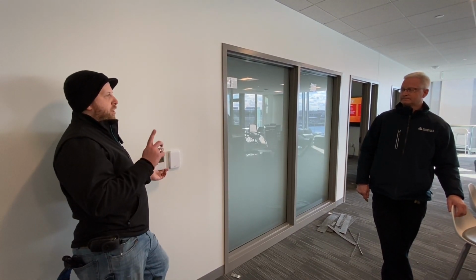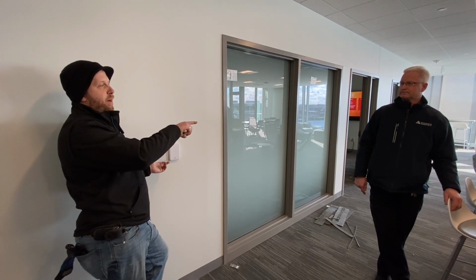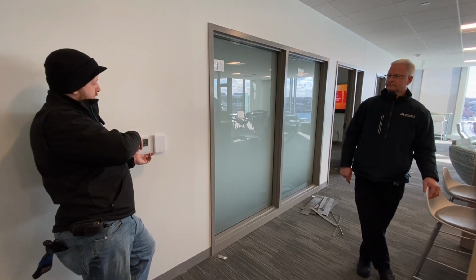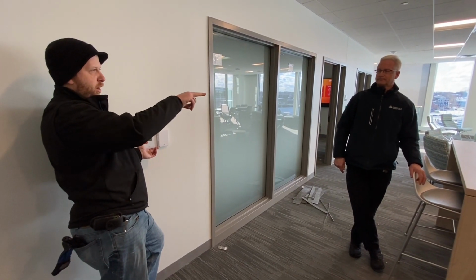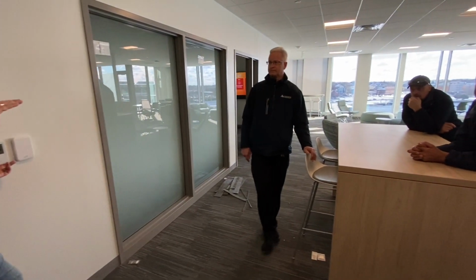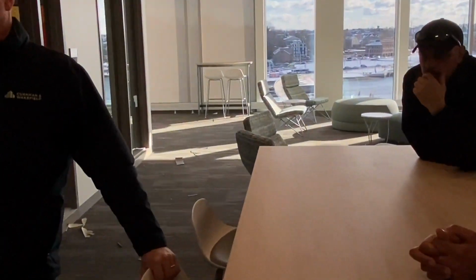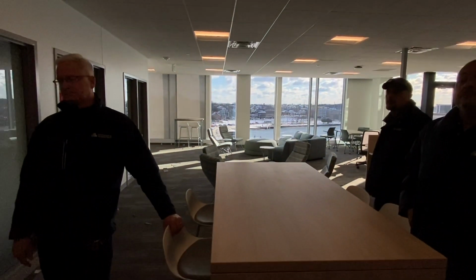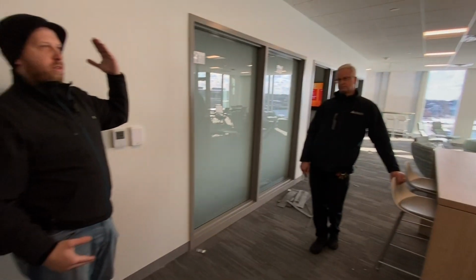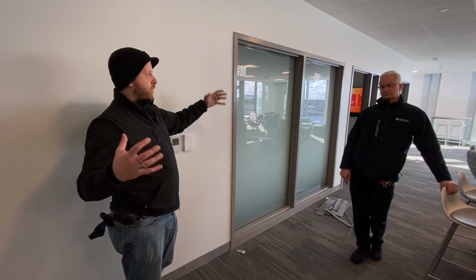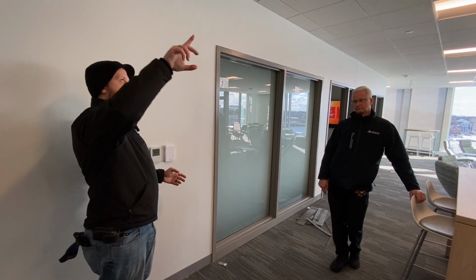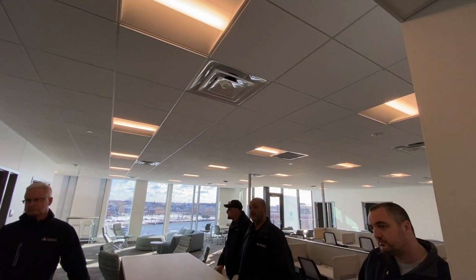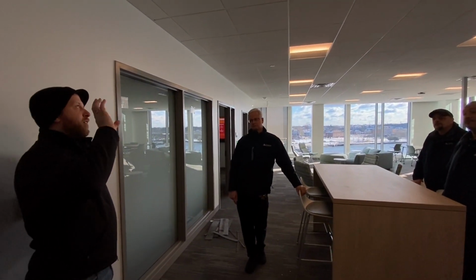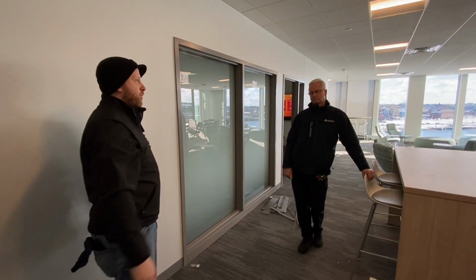Pretty straightforward. Most of these VAVs are on the perimeter, and our VAVs will also control the baseboard heating along under the windows. You can almost consider it like a 2-stage heating. We want to get the heat on the perimeter first, that way you're not having all the air sapped out through the windows. So first stage baseboard rinses the windows of heat, so you get that heat gap, and then we'll do the reheat in the box. Each one of these has a modulating reheat valve that heats up a coil and then maintains that 68.